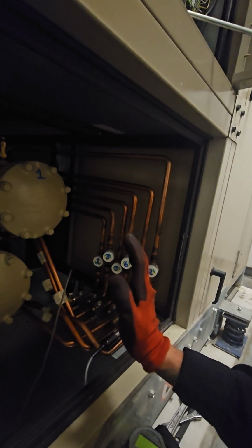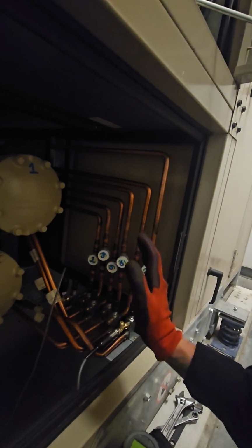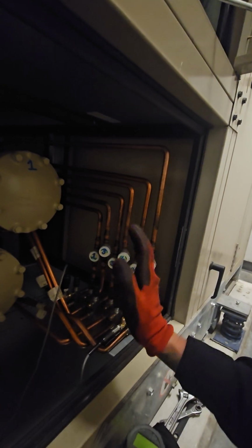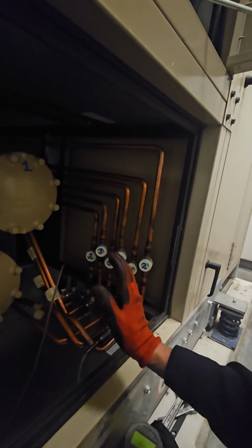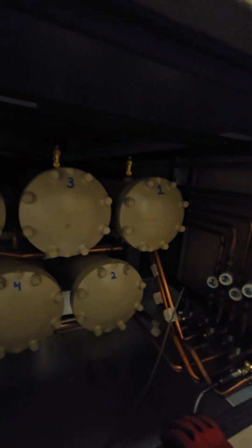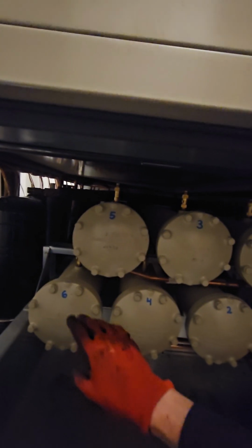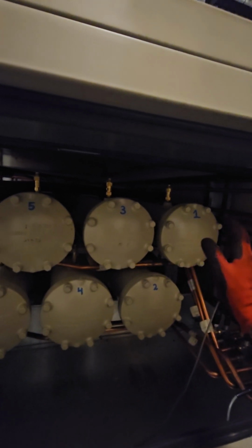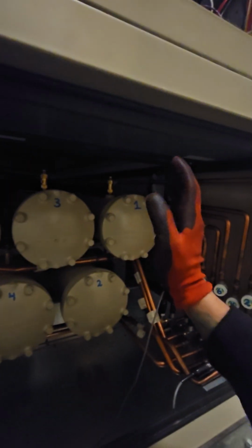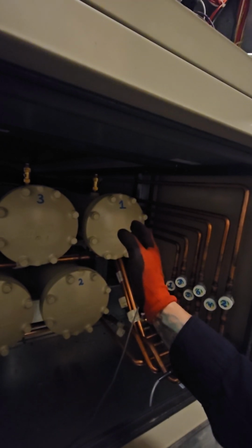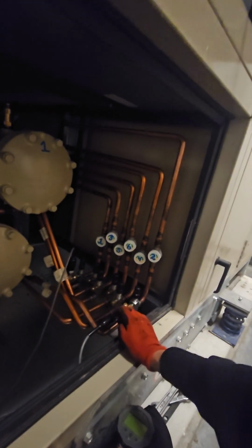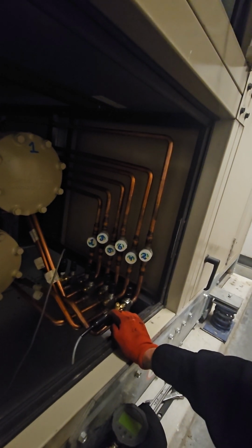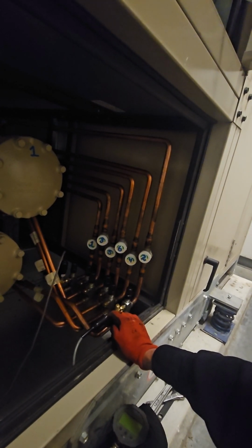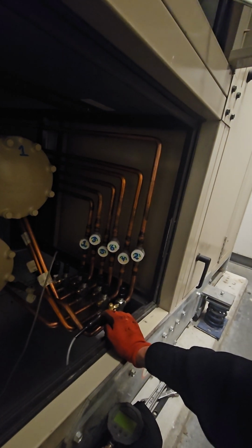They're not really their own circuit because they're all individuals, but they're kind of split off in halves. You know, 2, 4, 6, 1, 3, 5. But again, as you can see, each one of these is an independent system. There's compressor 1, and it has its own condenser. All of these have their own, but 1 and 2 are what throttle the water regulating valve. So in essence, it's almost like they split it up.